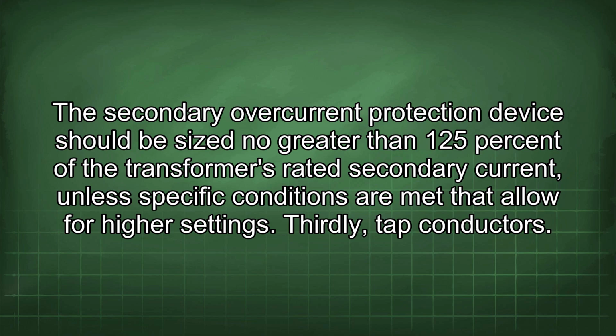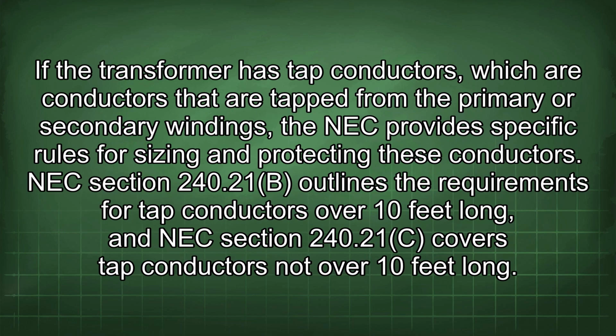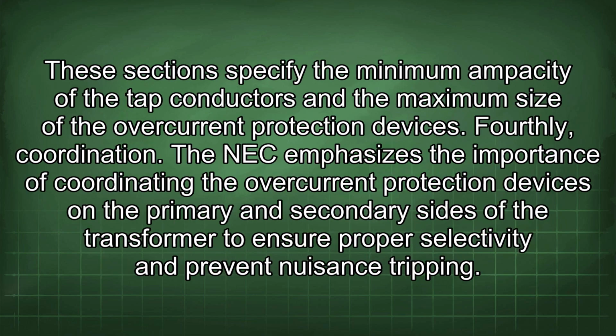Thirdly, tap conductors. If the transformer has tap conductors, which are conductors that are tapped from the primary or secondary windings, the NEC provides specific rules for sizing and protecting these conductors. NEC Section 240.21(B) outlines the requirements for tap conductors over 10 feet long, and NEC Section 240.21(C) covers tap conductors not over 10 feet long. These sections specify the minimum ampacity of the tap conductors and the maximum size of the overcurrent protection devices.